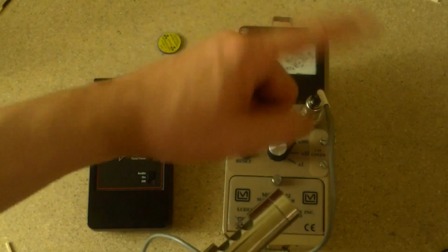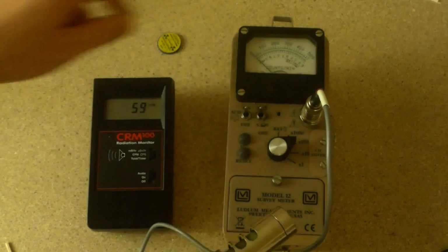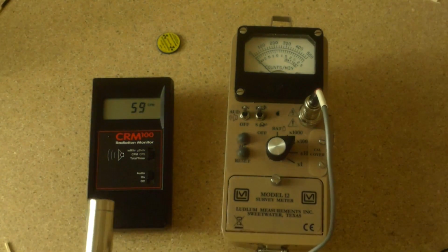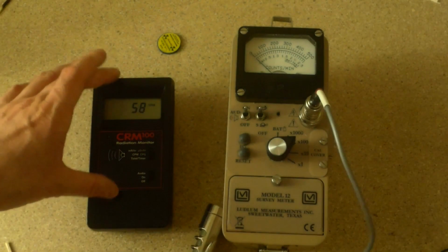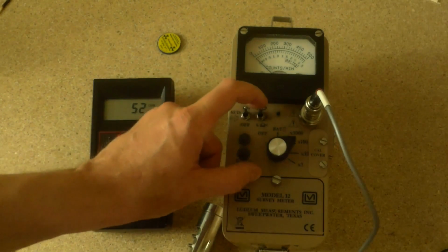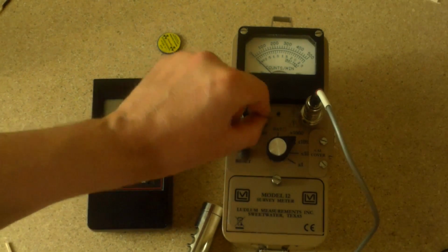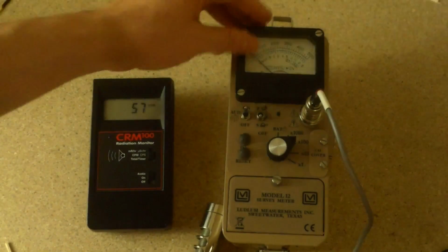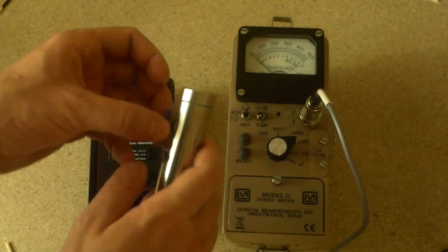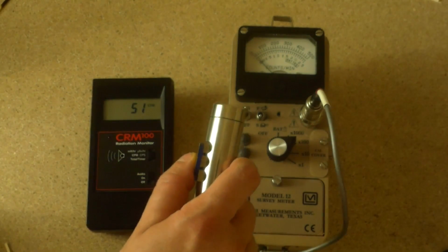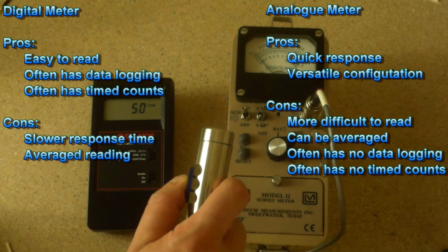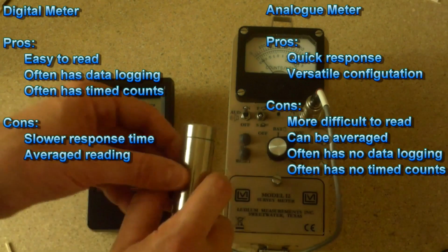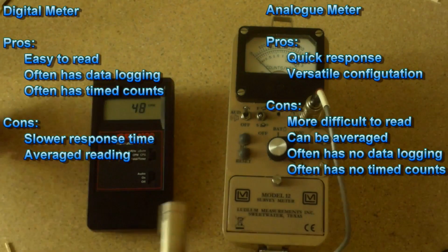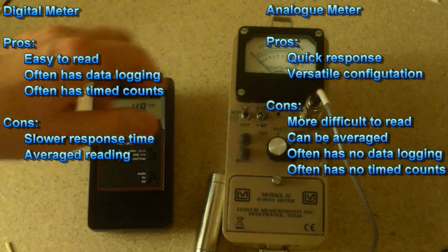Times 10, it's times 10. Times 100, times 1000. Some of them do auto scale, this one does not. If you want, however, to get some of the same functionality you get out of this guy with accuracy, you can switch to the slow motion setting. A lot of these type of detectors have this. It takes longer to get to the actual reading, but it's much more precise and doesn't move around as much. And you hit the reset button to go back down again. So it kind of depends on what you're looking for.